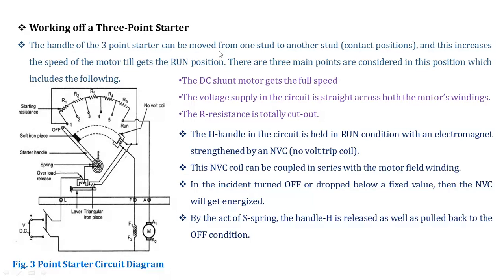So the handle of the three-point starter can be moved from one stud to the other, that is, from one contact position to another, and this increases the speed of the motor until it reaches the run position. We can move the handle from the off position to the run position by contacting these studs. Three main points are considered in these positions. First, the DC shunt motor gets full speed. Second, the voltage supply in the circuit is applied straight across both the motor windings, and the resistance R is totally cut off in the run position.